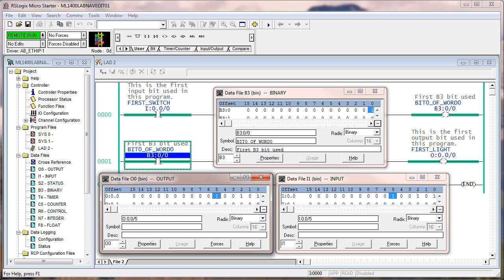Now, there was a question in there. If I flip on 0, 2, and 5 to the on state, will this change the state of output 0? No, it will not, because it does not affect the logic that is controlling output 0. Those things we turned on and off, none of them are used in the ladder logic.